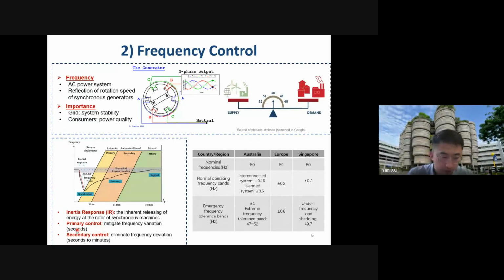And importantly, you should know primary control is faster. It immediately acts within several seconds, and it aims to instantaneously mitigate the frequency deviation, the frequency decline. After that, the secondary control system is relatively slower. However, it aims to fully recover the frequency back to normal. And here, I have also listed the tertiary control. Tertiary control is mainly for economic dispatch, especially for economic dispatch.